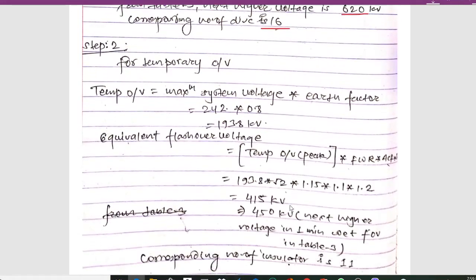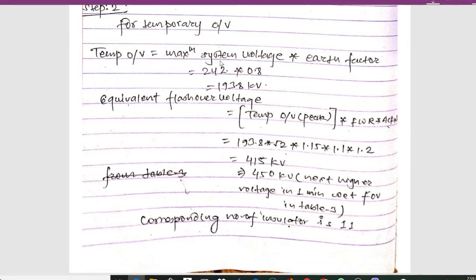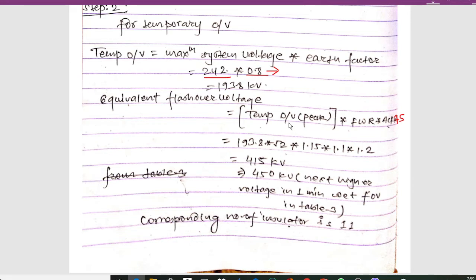In Step 2, for temporary overvoltage: temporary overvoltage = maximum system voltage × earth factor. Maximum system voltage is 242 kV and the earth factor is assumed as 0.8, giving temporary overvoltage as 193.8 kV. The equivalent flashover voltage = temporary overvoltage (peak) × FWR × ACF × FS. For peak we multiply by √2, so: 193.8 × √2 × 1.15 × 1.1 × 1.2.